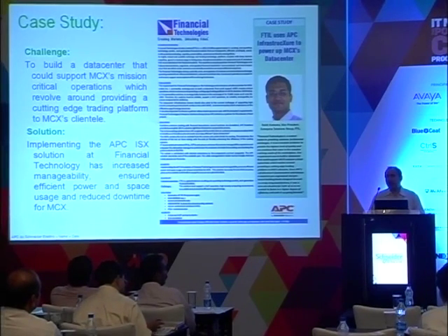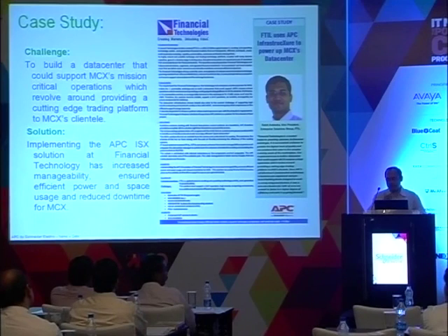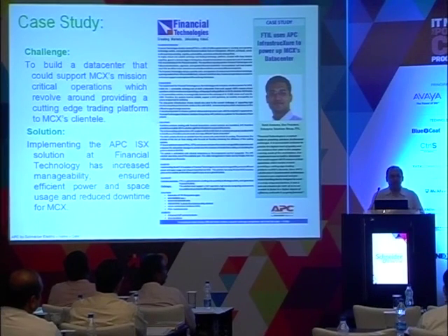A case study in point is this data center. It's approximately a 1 megawatt data center design, wherein the first phase, it was modularly built, first phase of half, that was built, 500 kilowatts. The client wanted an architecture which could last 10 years, and they wanted to bring in all the efficiency benefits and so on. So right from space optimized, efficiency of UPS system optimized, modularity in design, high efficiency cooling systems deployed which can control high density equipment as well as low consumption of energy and so on and so forth. By doing this, they were able to see up to 30% of reduction from the earlier data centers that they were using. Simple benefit is PUE, right?